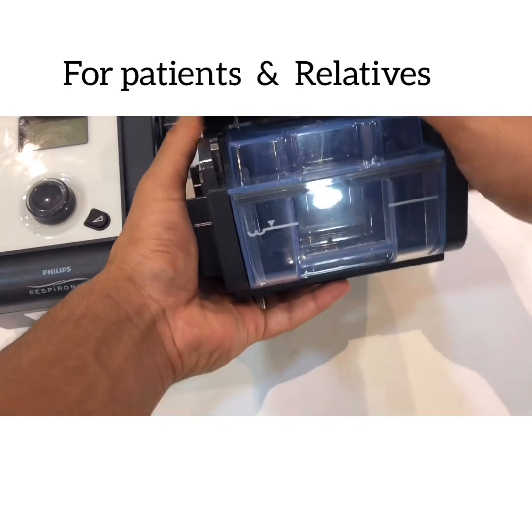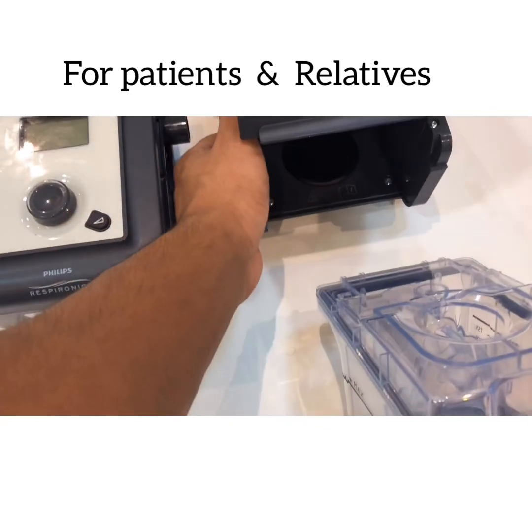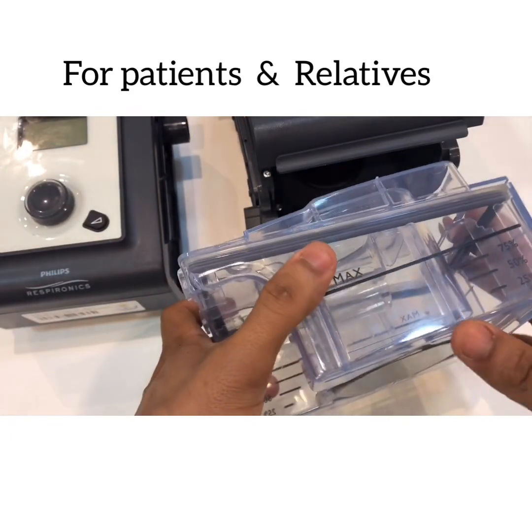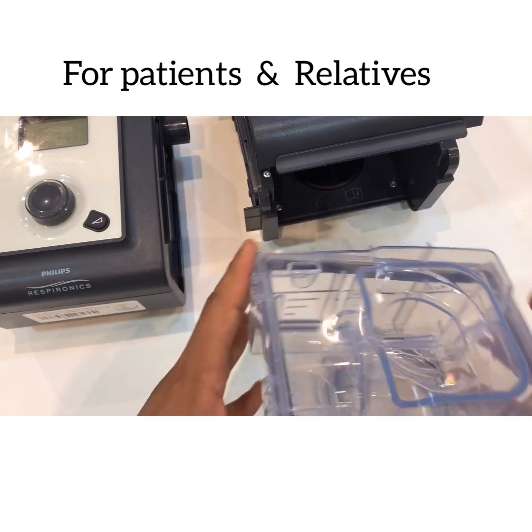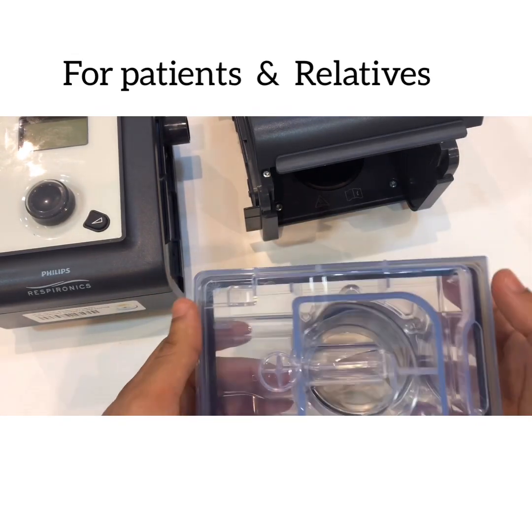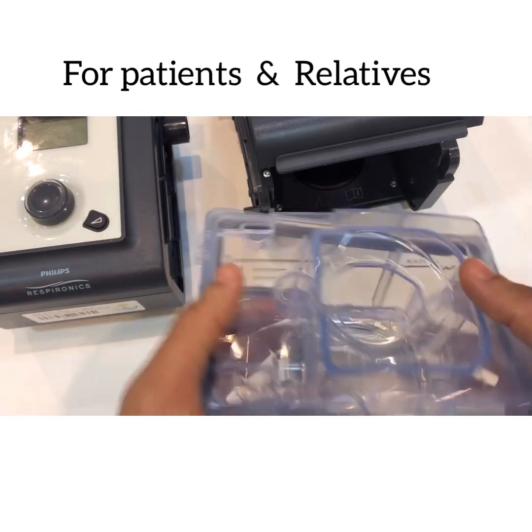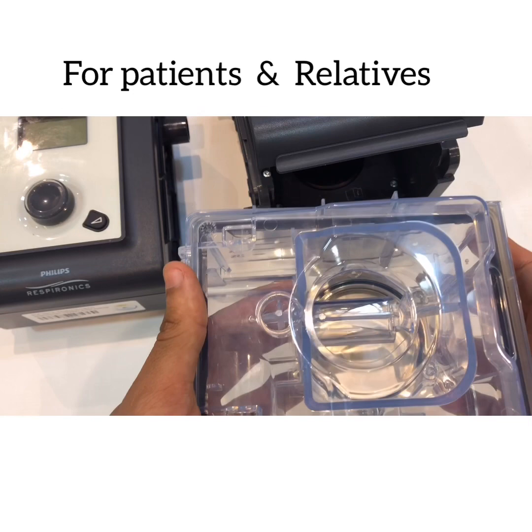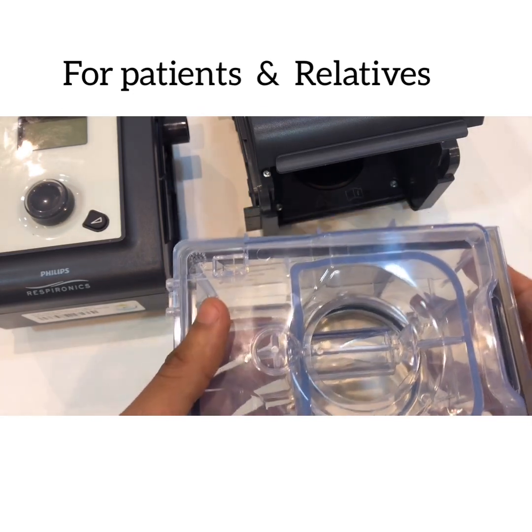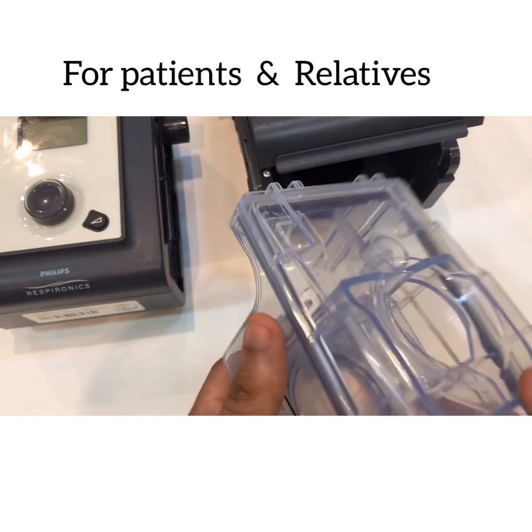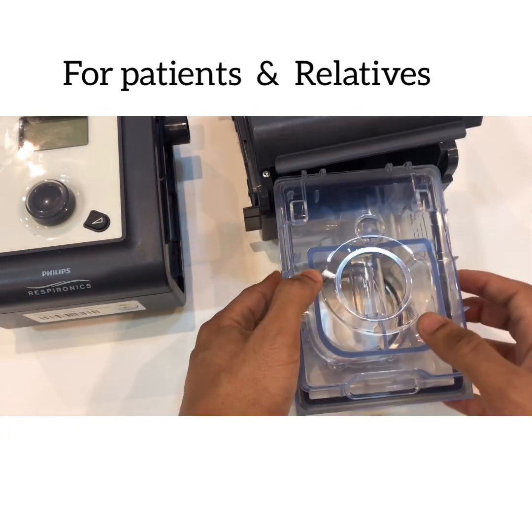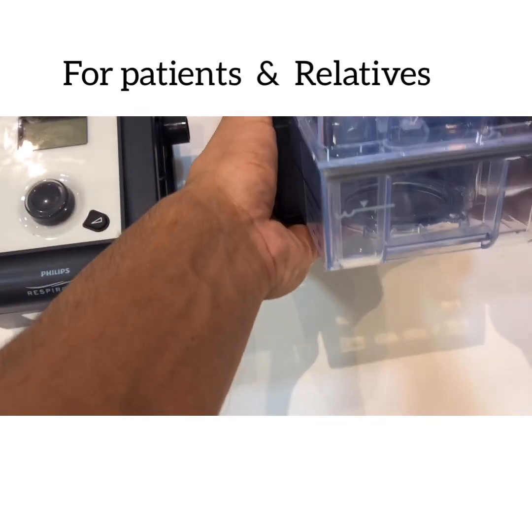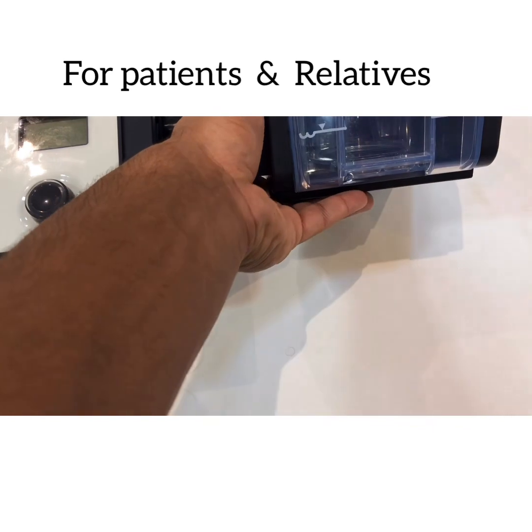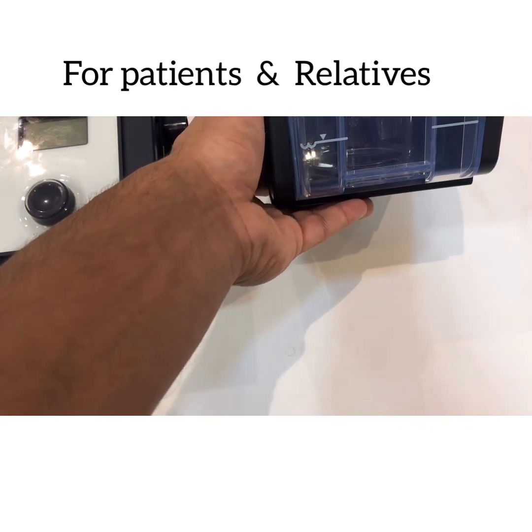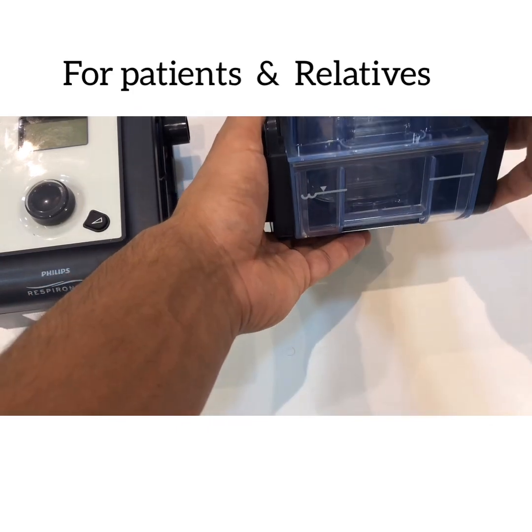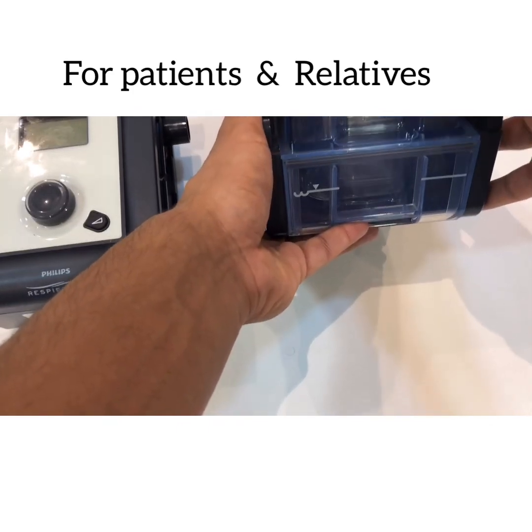So I will remove it. I will check the level of the water. I will make sure there is no crack and it's not leaking from the chamber. Then I will slide it in after filling the chamber with new water. Distilled water is the recommended one. However, we can use any kind of water as long as it doesn't have material that affects the airway. It is very important to make sure that the chamber itself can be slid in very easily, smoothly, with no resistance, because if there is resistance, that means this is not the appropriate size of chamber and we have to change it.